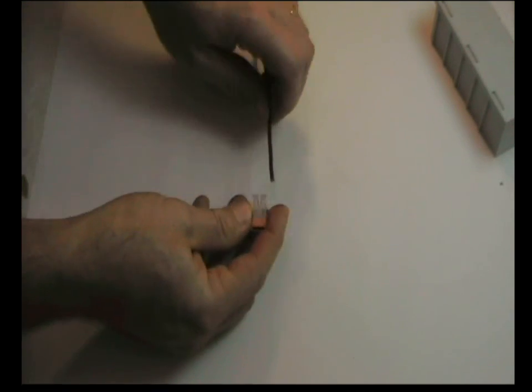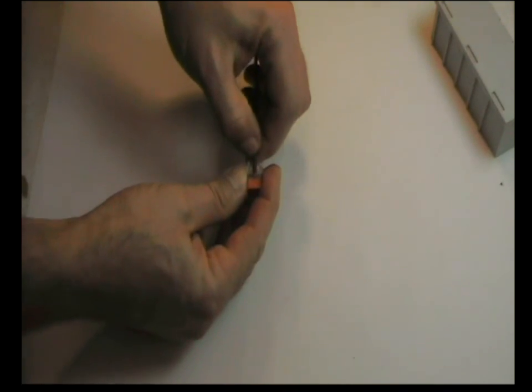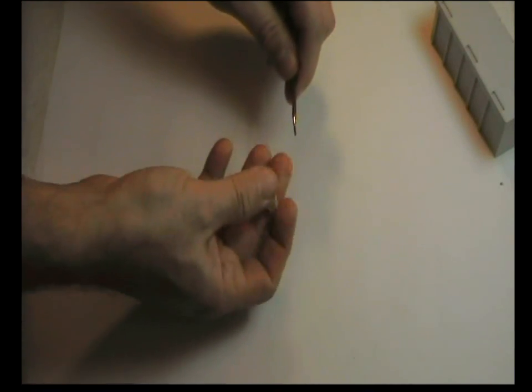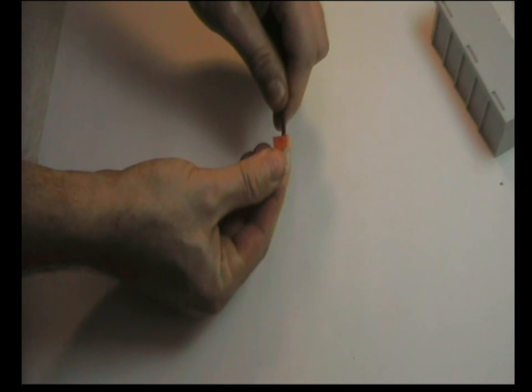We'll start with this 4-way. If you look on the back of the 4-way, you'll actually see that there's a slight guide there, and that guide, if you lay the cable in there, gives you a trim distance of about 11mm. So if we take this and trim off that much, you can see the cable, and we just push it into the connector like that.